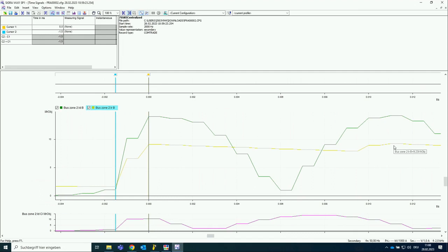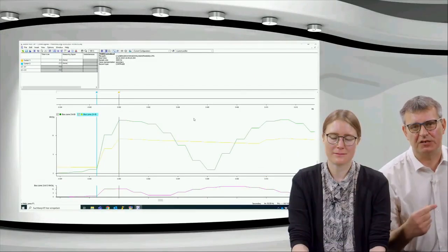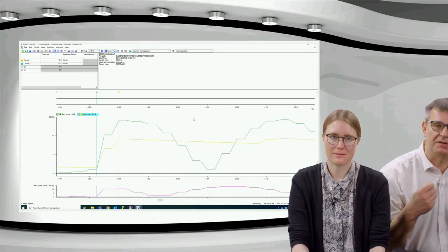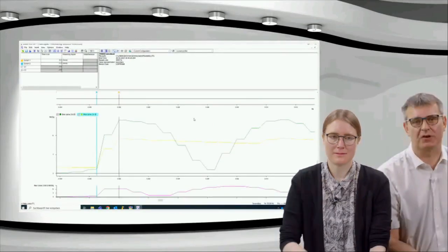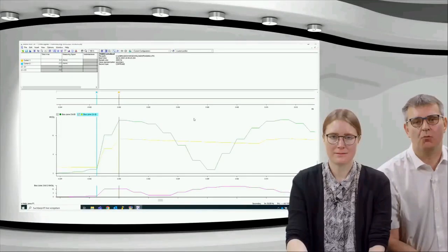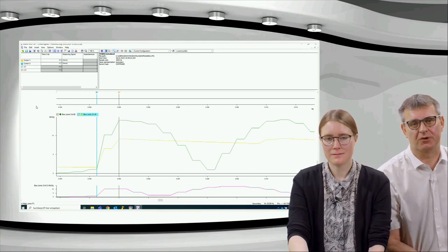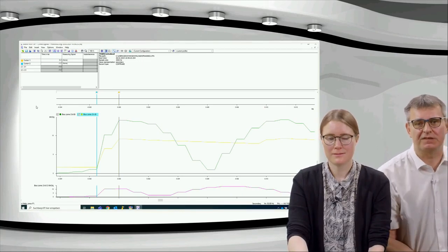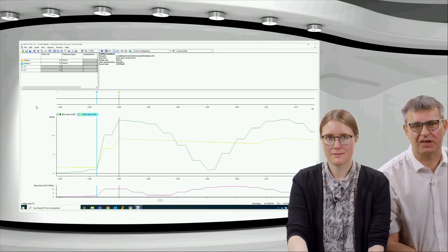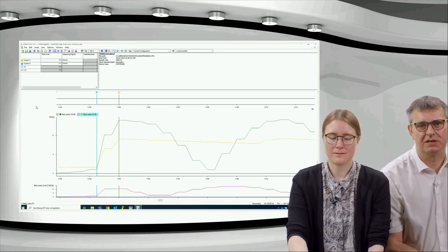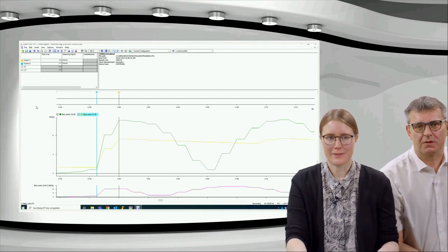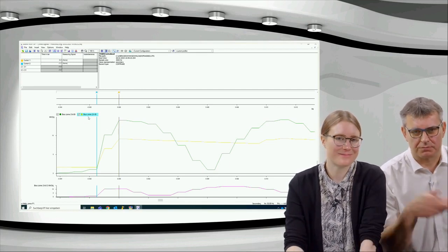But still more, we are seeing here not the modified stabilization current. We are already seeing the modified stabilization current multiplied with the stabilization factor. That means if the differential current is above this line in the fault record, we can directly state we are in the tripping area. As soon as the differential current is above the characteristic of the modified stabilization current multiplied with the stabilization factor, we can say, okay, we are in the tripping area.